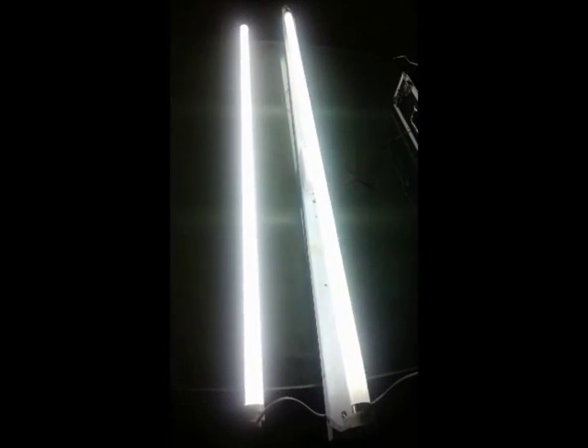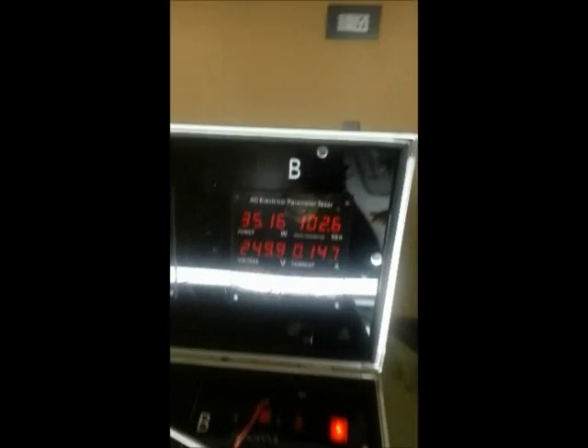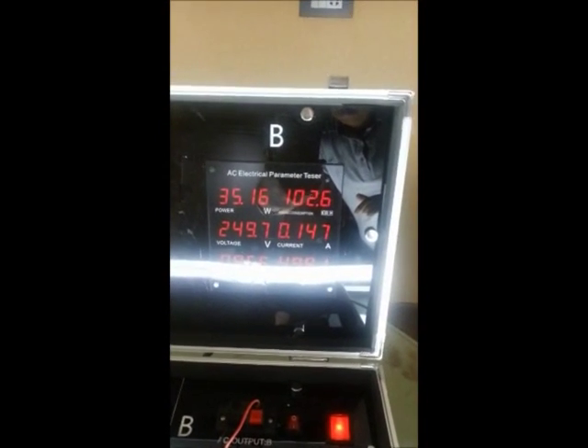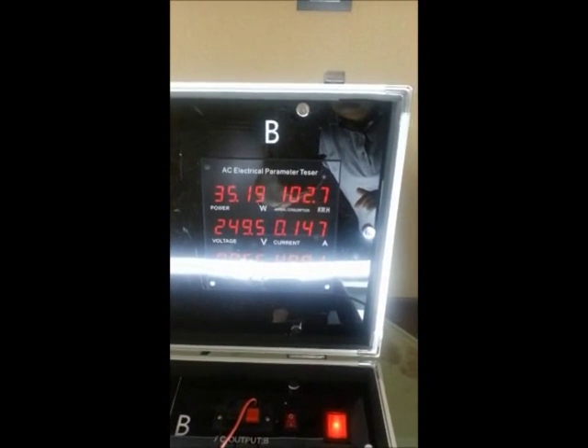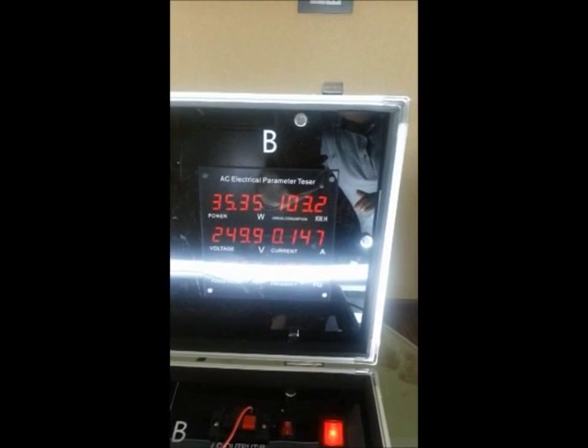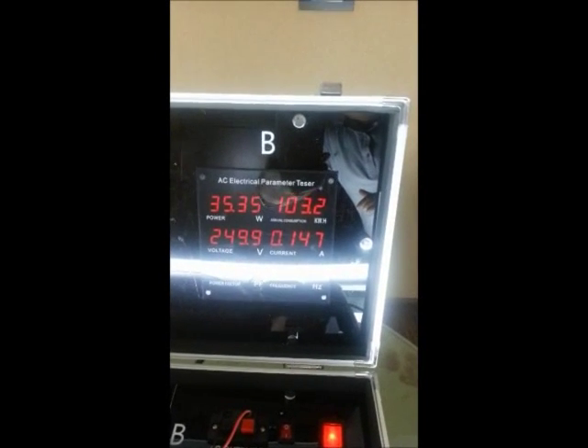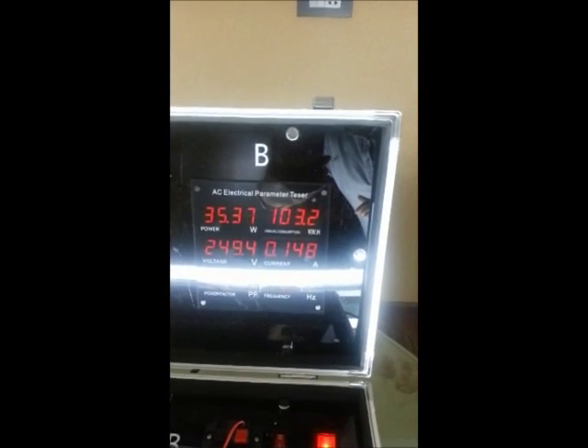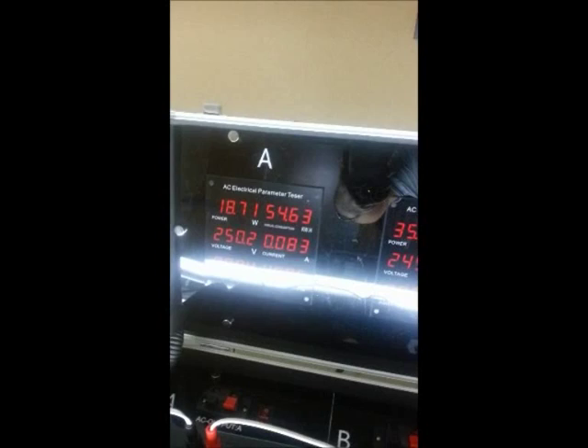Now we are showing you the comparison between the tube light with the electronic choke and our Millennium T8 LED tube light. The tube light with the electronic choke is consuming almost 35 watts while the LED tube light is still consuming 18.7 watts - almost half of the consumption.